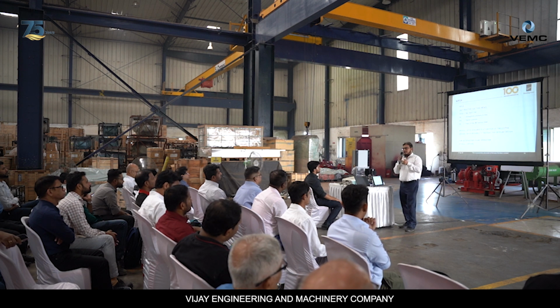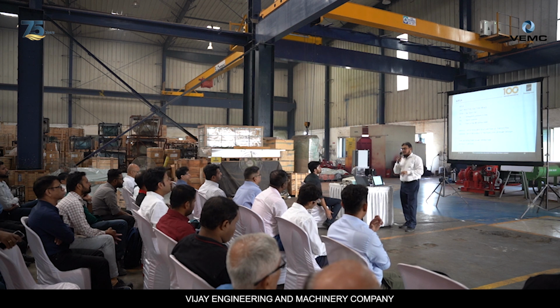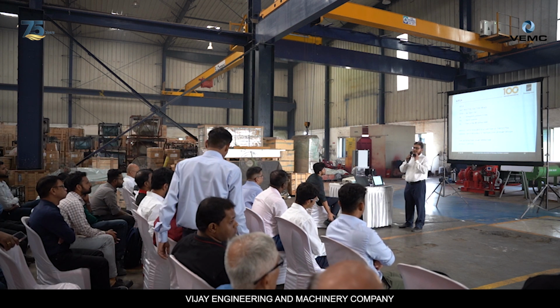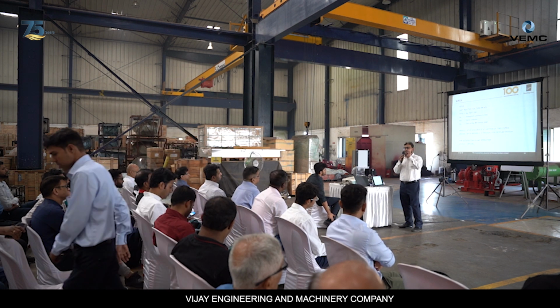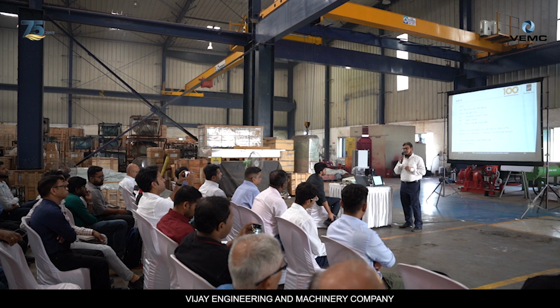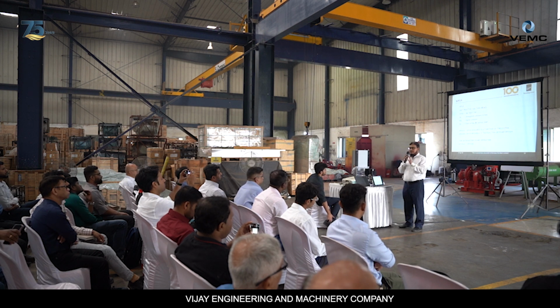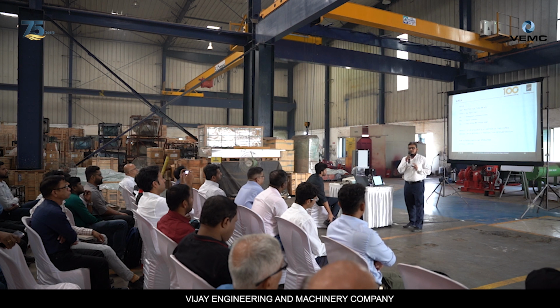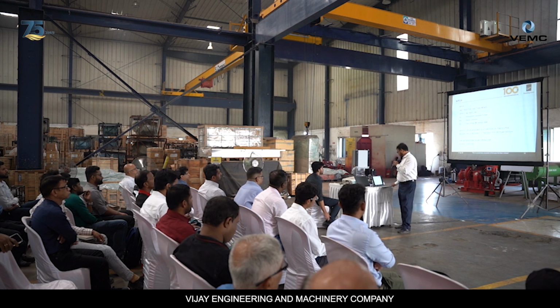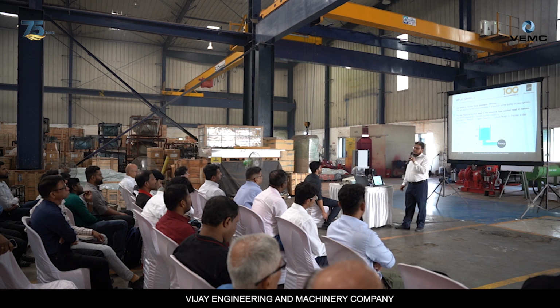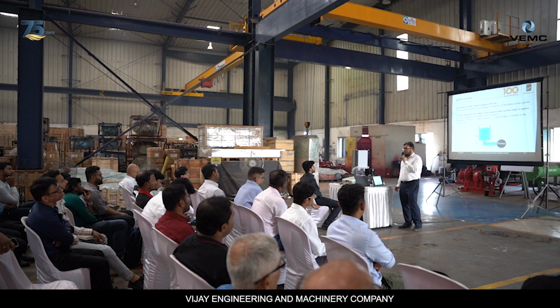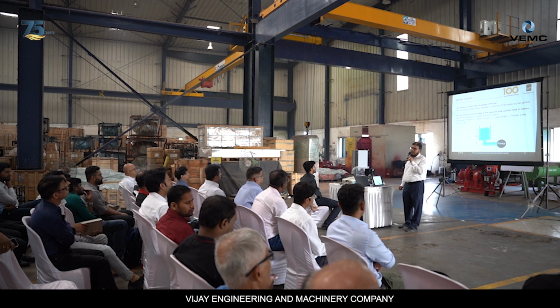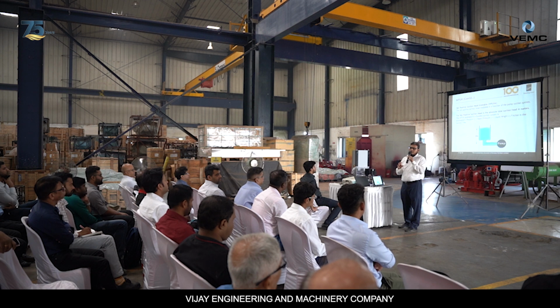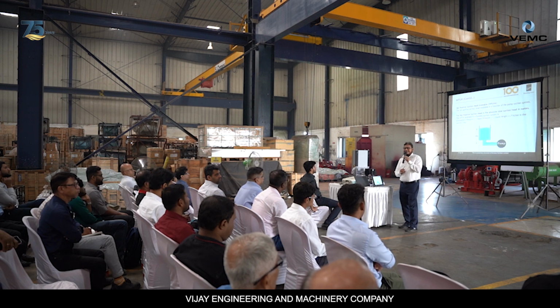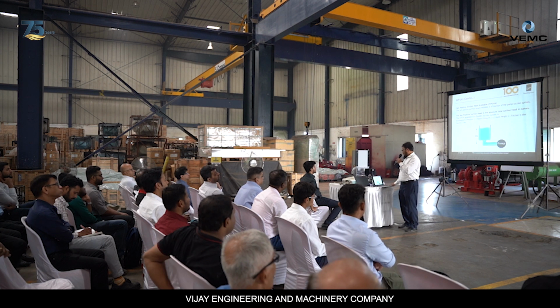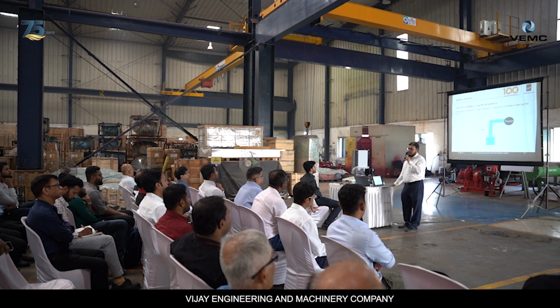NPSH is very important. I am showing you another earlier slide: net positive suction head available and required is used to categorize whether the pump is performing. NPSH A is always greater than NPSH R. This is the thumb rule of the pump, and then the pump will work. The difference between NPSH A and NPSH R is 1 meter. This net positive suction head is calculated on the vapor pressure, atmospheric pressure, friction loss in the pipeline, and the condition like an above ground water tank or below ground water tank. If it is a below ground water tank, then this will also be calculated while you select the pumps.